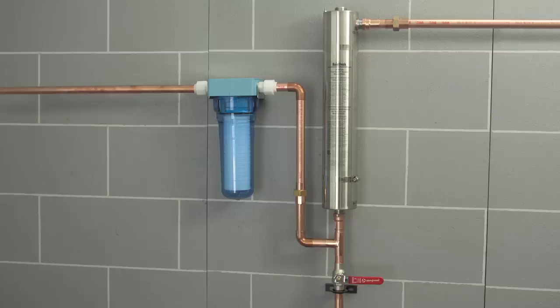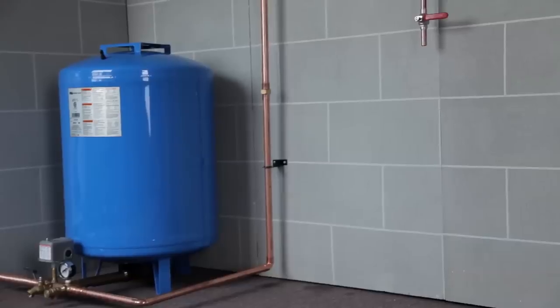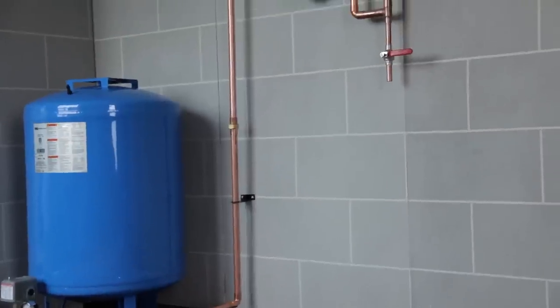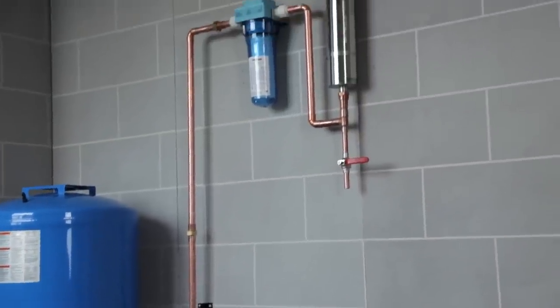The UV system disinfects all the water in the house and should be installed after your existing pressure tank. While some waters require additional pre-treatment, a 5 micron sediment filter should always be installed before the UV.